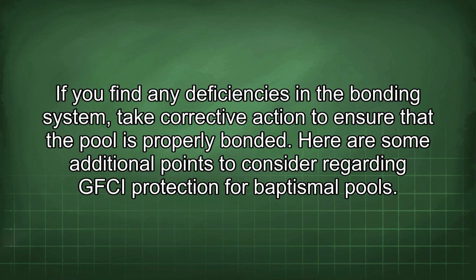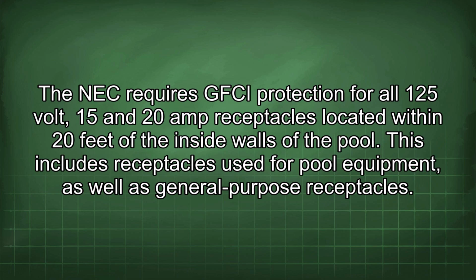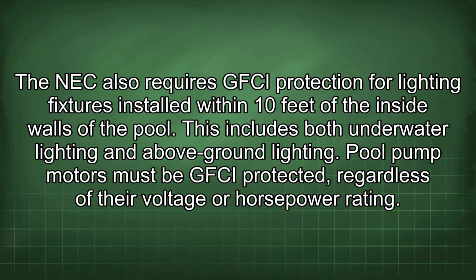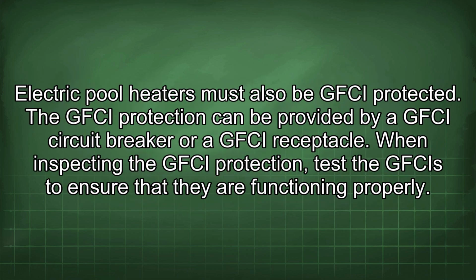Here are some additional points to consider regarding GFCI protection for baptismal pools. The NEC requires GFCI protection for all 125-volt, 15 and 20 amp receptacles located within 20 feet of the inside walls of the pool. This includes receptacles used for pool equipment, as well as general-purpose receptacles. The NEC also requires GFCI protection for lighting fixtures installed within 10 feet of the inside walls of the pool. This includes both underwater lighting and above-ground lighting. Pool pump motors must be GFCI protected, regardless of their voltage or horsepower rating. Electric pool heaters must also be GFCI protected.